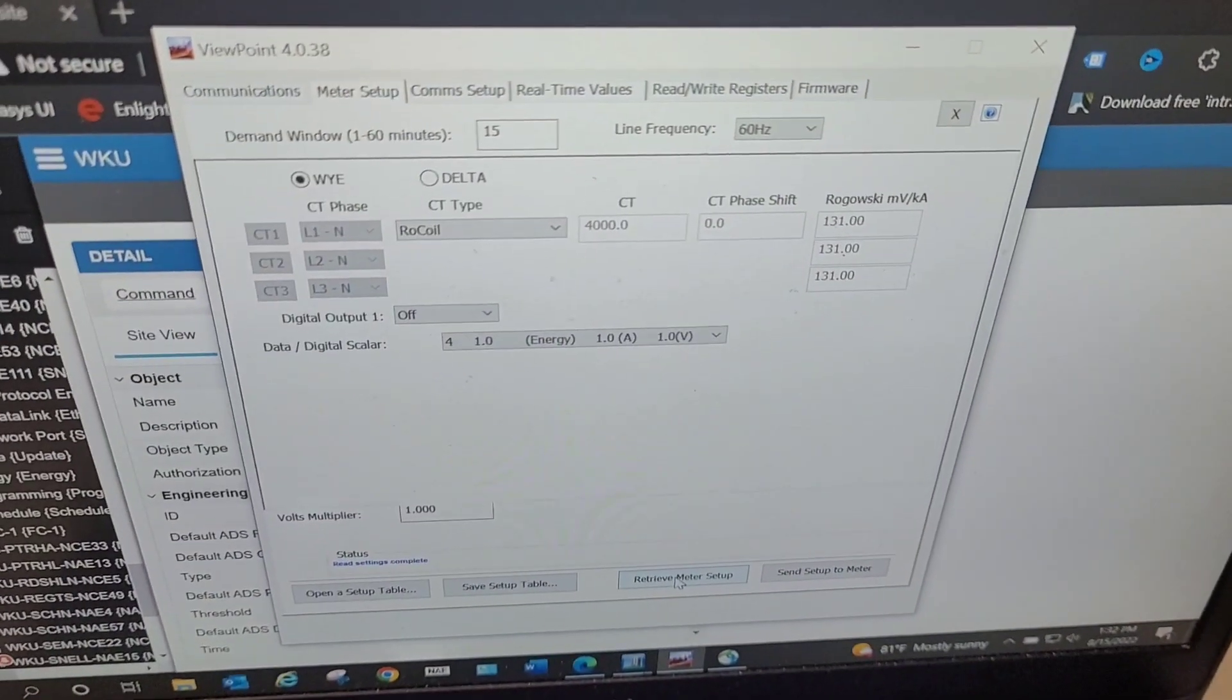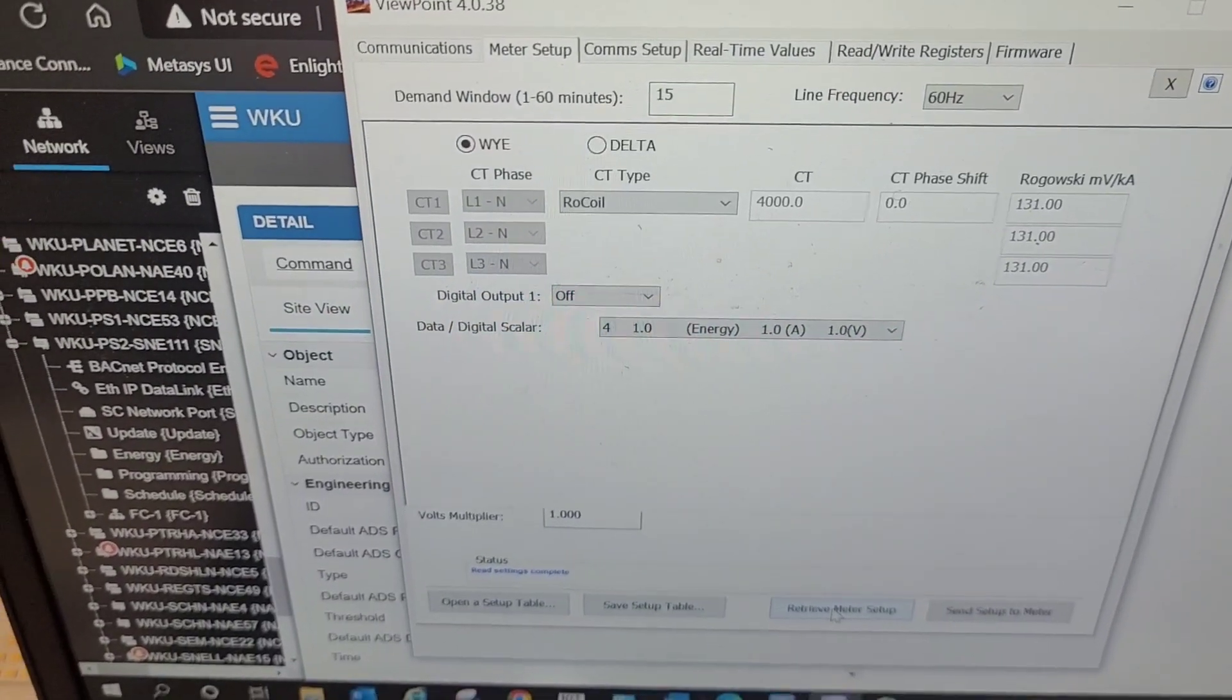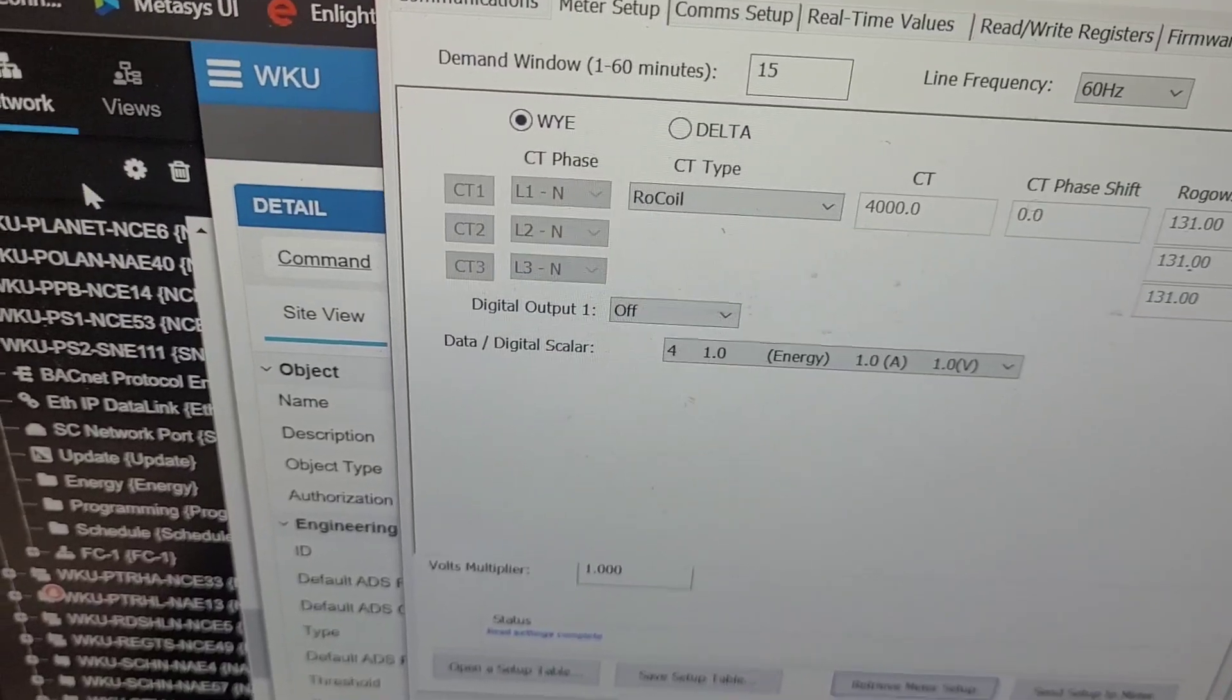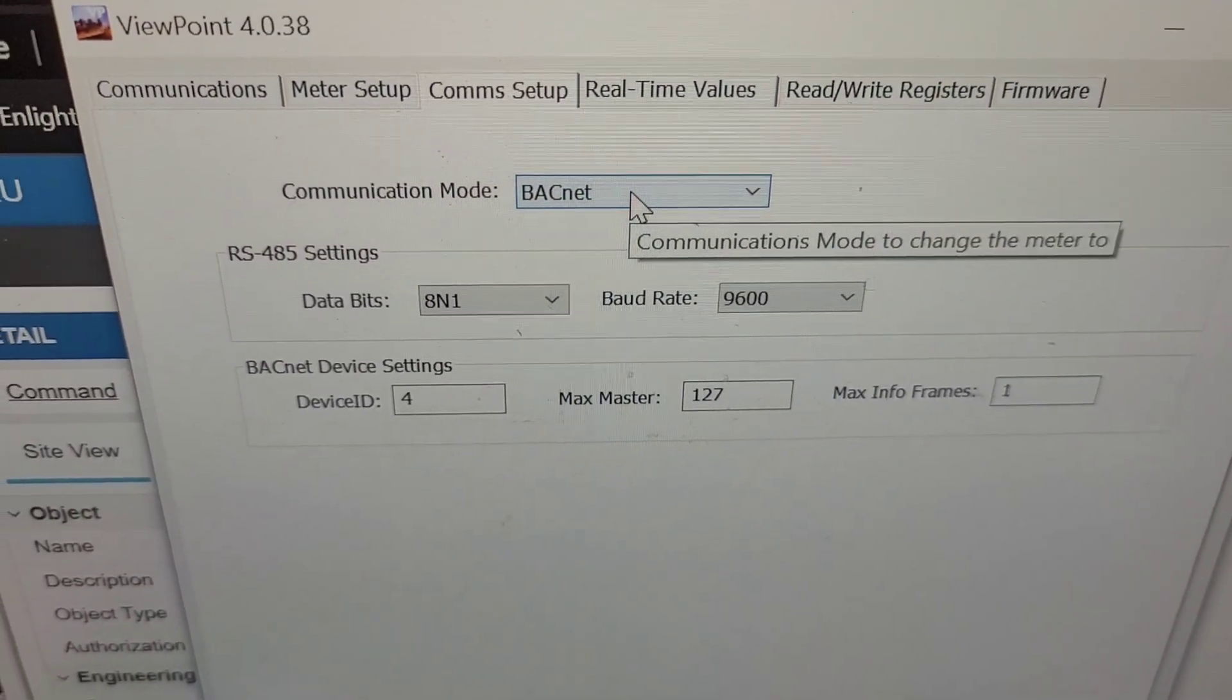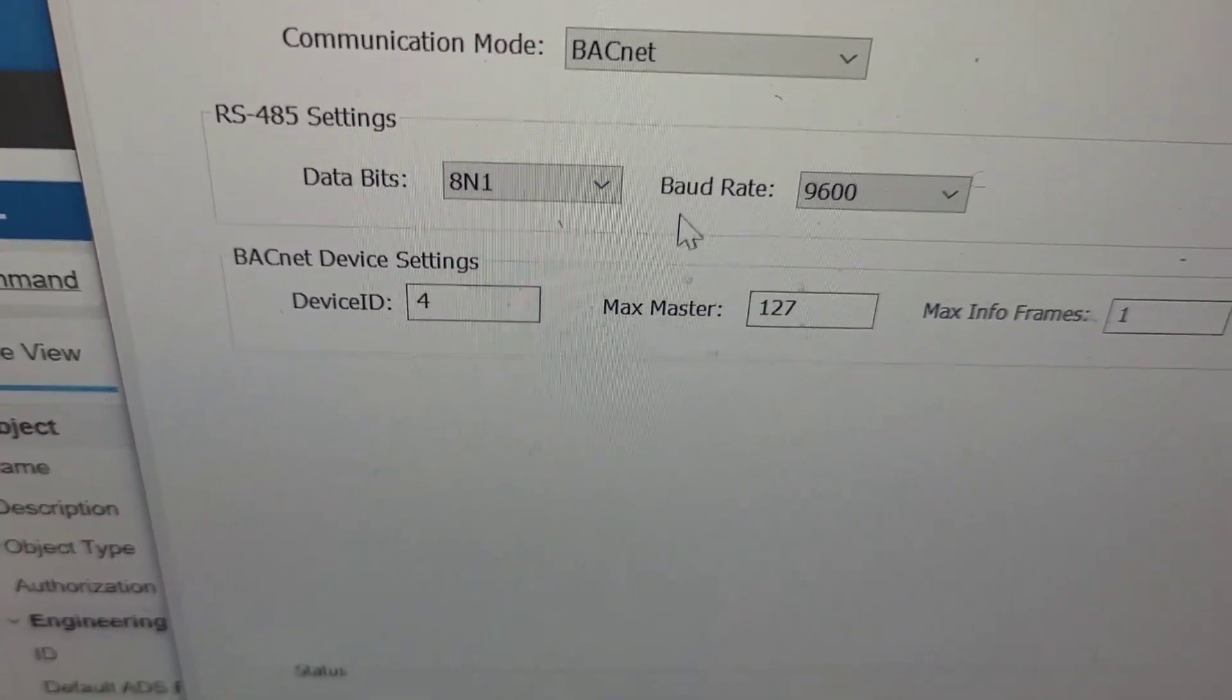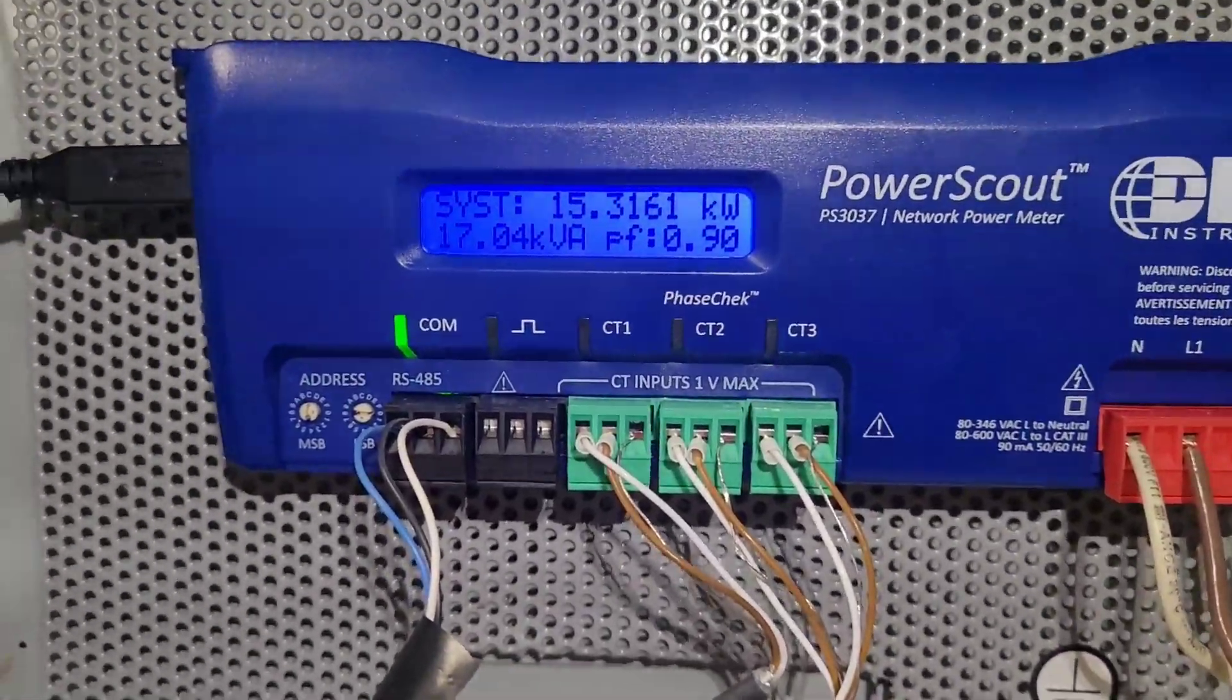Okay, guys. I just thought I would show you just a little bit about the Viewpoint software. This is the software that you would use for setting up the Dent Power Meter. And you can see here from this screen, this is where I would select the CT type, whether or not I am a Y Delta, that sort of thing. And it is there again. It's very easy, very intuitive to do this. Now, your communication setup for these meters, this is something here. What you will need to make sure of here is that you select the proper communication options. You make sure also that you set all of your baud rate and things like that properly as well. Set your device address, any kind of identifiers, things like that. If you do not have this setup correctly, your meter is not going to communicate. Okay, now I have already got this meter configured, as I mentioned earlier, but I just wanted to take a few more minutes and just show you a little more details about this.